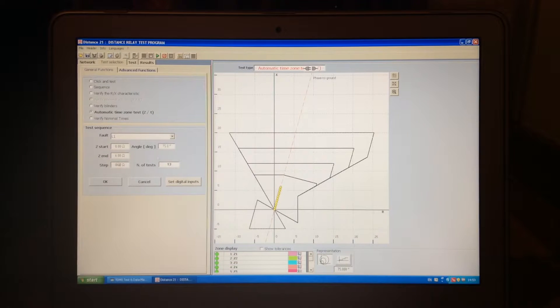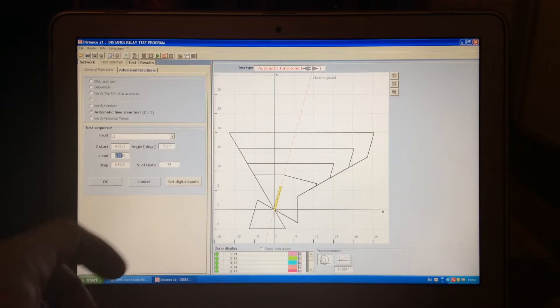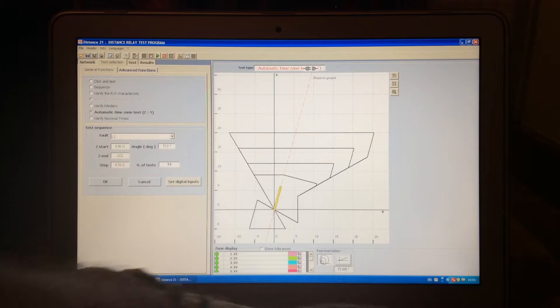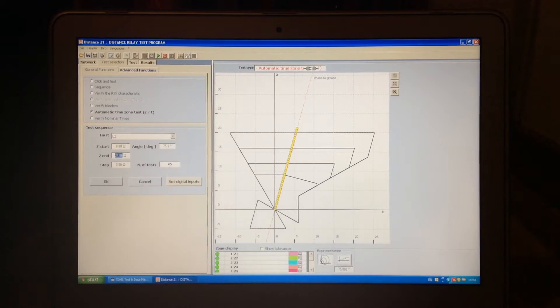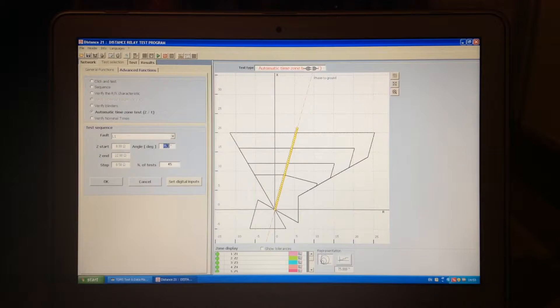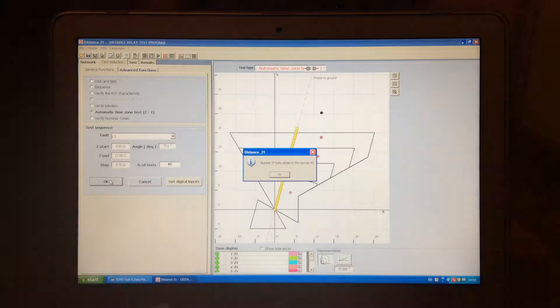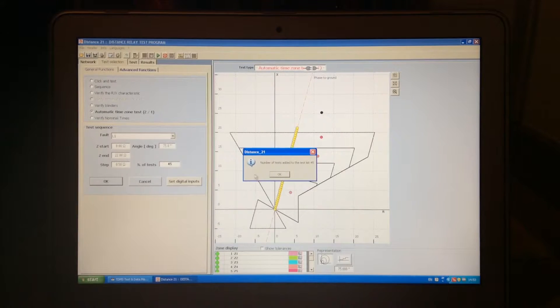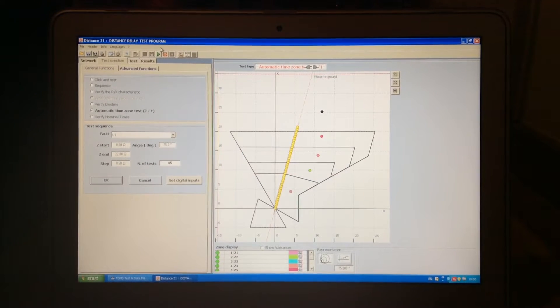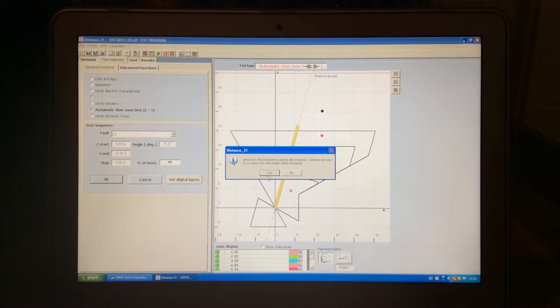Automatic time zone is a standard test, where you set up the initial impedance and the end impedance together with the step, and you define the angle, which is the angle of the overhead line usually. You press OK, and now in this case, we can also simulate the result for this.